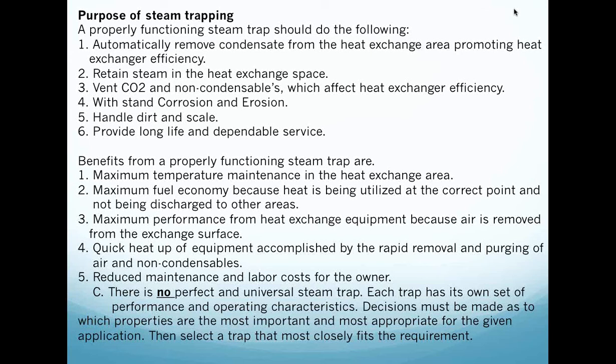In steam trapping, a properly functioning trap should automatically remove condensate from the heat exchange area and promote efficiency. It should retain steam in the space. We're trying to use the latent heat of vaporization, the BTUs that we actually have in the steam. We would vent the CO2 and the non-condensables, so carbon dioxide non-condensables, which affect the heat exchanger efficiency.